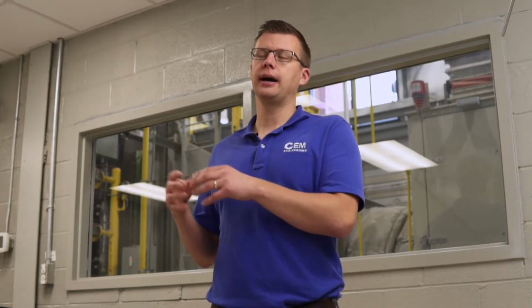38 kV class. That gear here is interesting. It's outdoor rated gear, and it has a breaker in it for transformer protection. It has a breaker in it for islanding the plant. And so in the event of a utility trip or some other event on the grid, that breaker in that 27.6 switchgear can automatically island the whole campus here at Campbell's, and they continue to ride through any event. And so that's all integral to the 27.6 switchgear.